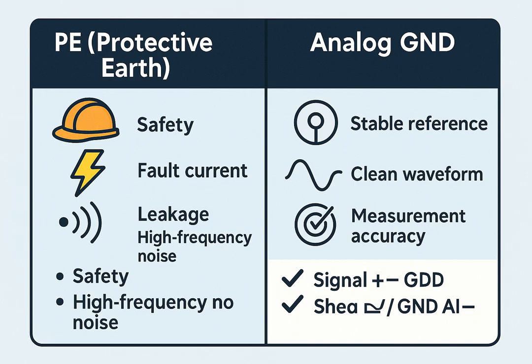Wiring checklist for analog sensors. Signal plus goes to PLC AI plus / I plus. Signal minus / GND goes to AGND / AI minus of the PLC. Do not use PE as the main return for sensor GND. Use shielded cable for long runs or noisy areas. Connect shield to PE at one end only. If two systems have different grounds, use a signal isolator. Keep analog cables away from VFD and motor power cables.